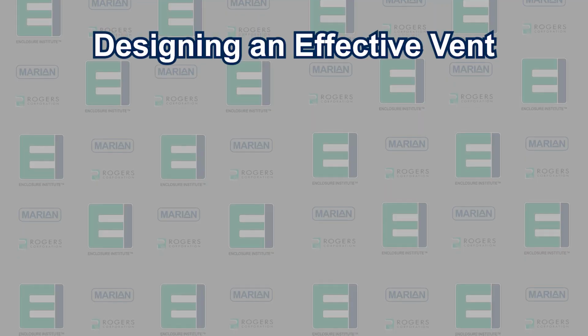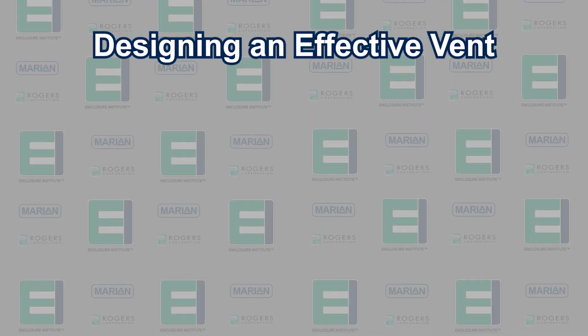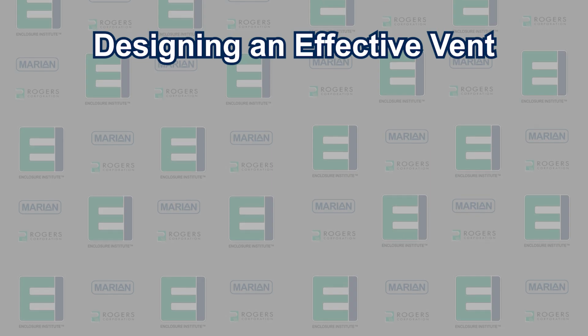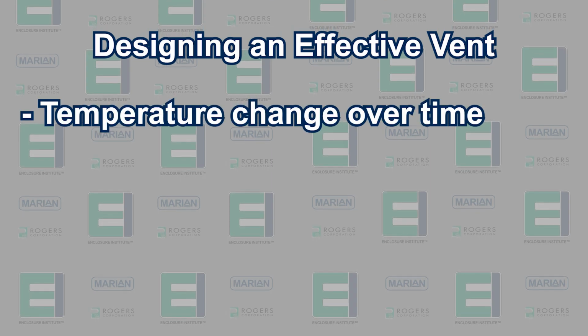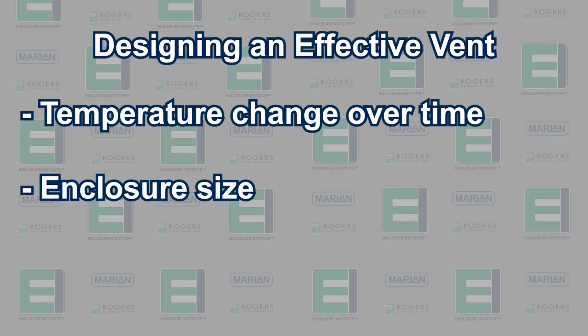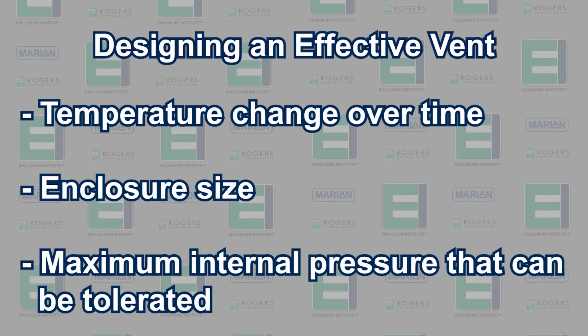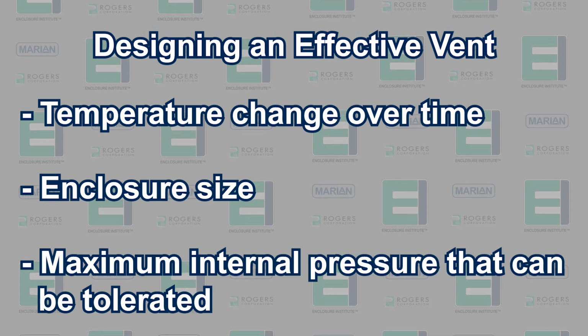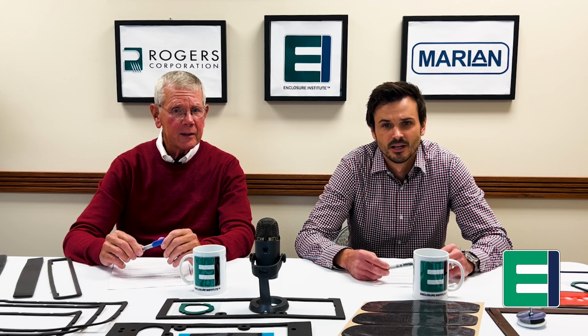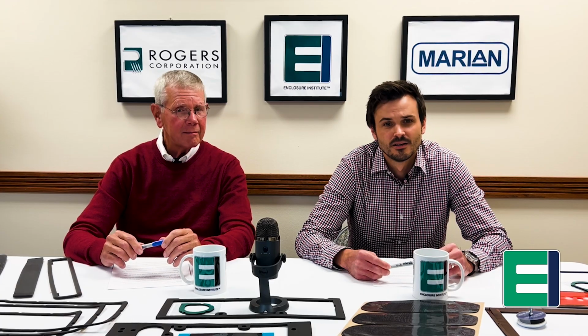Designing an effective vent for an enclosure involves first understanding operating conditions of your device, such as the temperature change over time that is expected, the enclosure size, and the maximum internal pressure that can be tolerated. The engineers at Rogers and Marian can help you select the best fabric and design to fit your device.